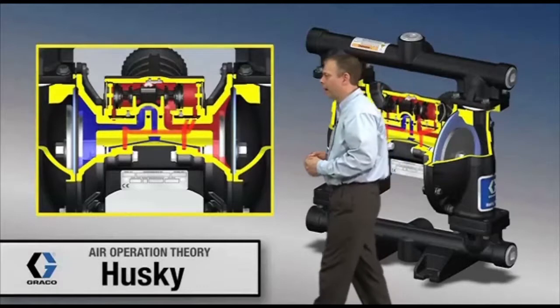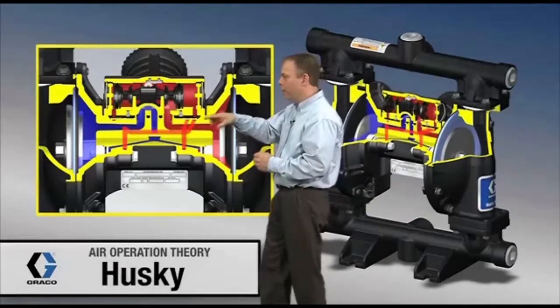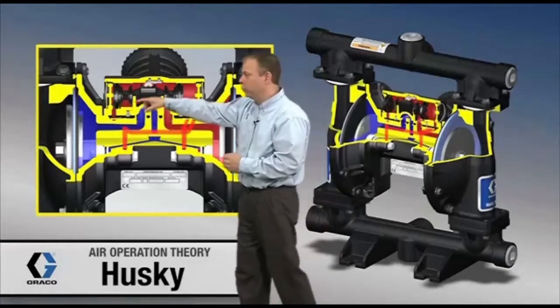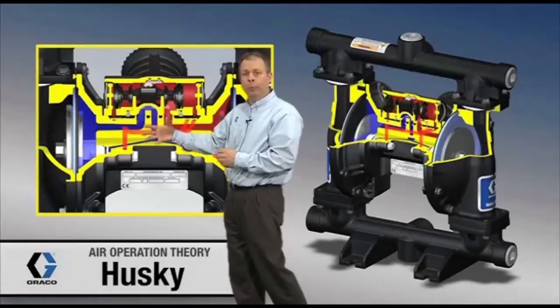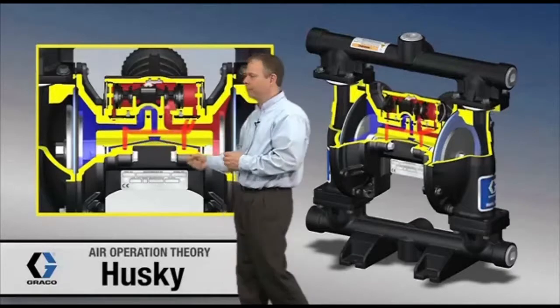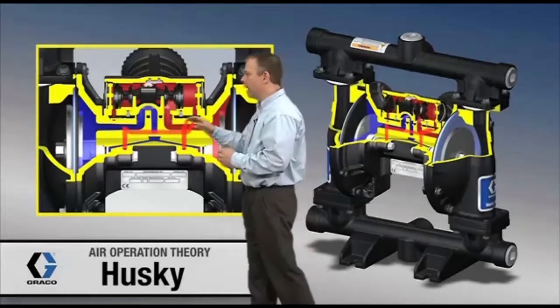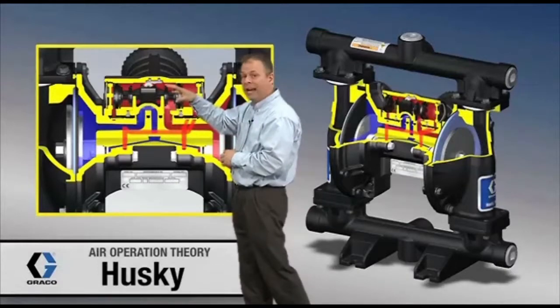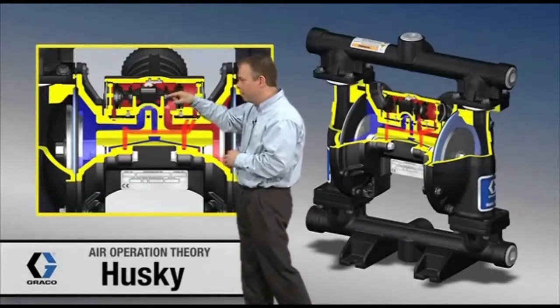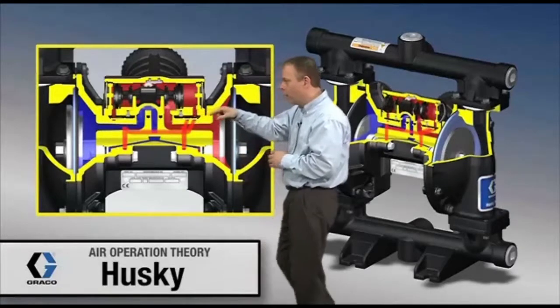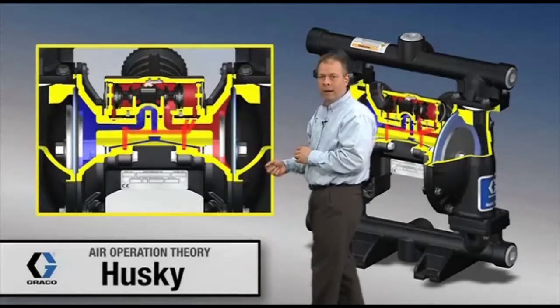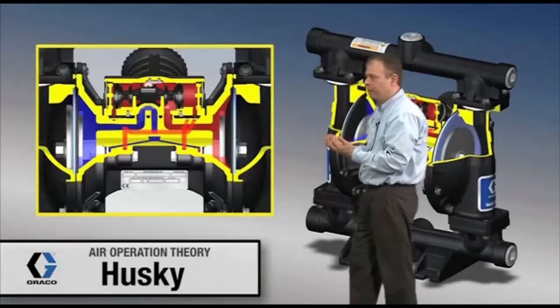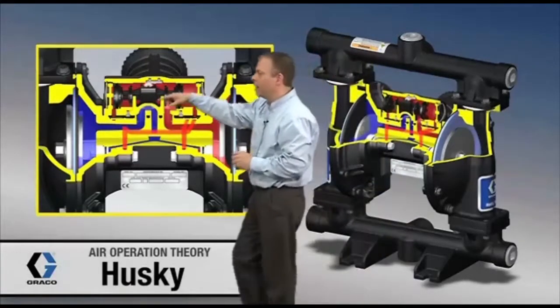The red indicates high pressure air, and the blue on the other side indicates low pressure or venting air. Right now we've got high pressure air in this module — this air valve — and it's piped down through here, all the way back to the back side of that diaphragm. That's what's causing the diaphragm to move in this direction.